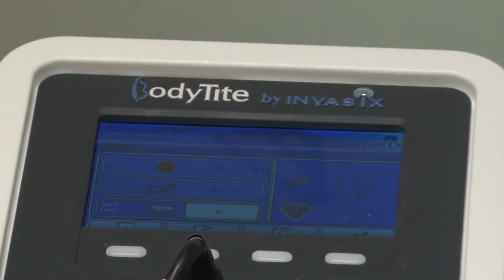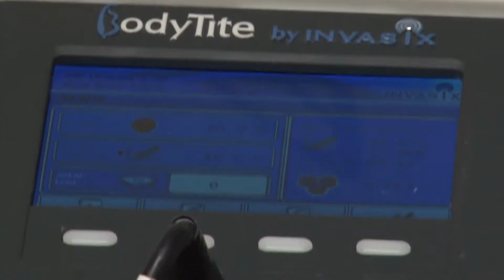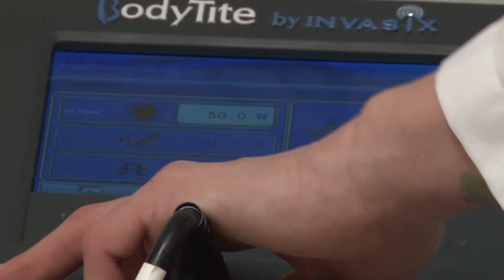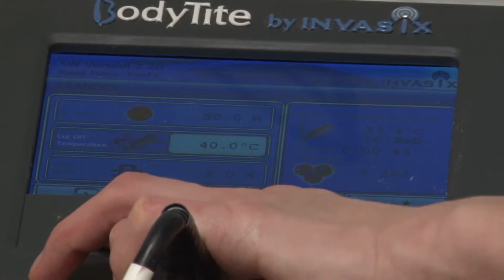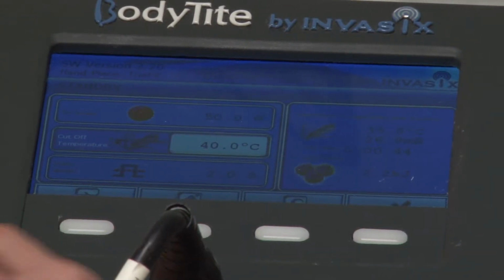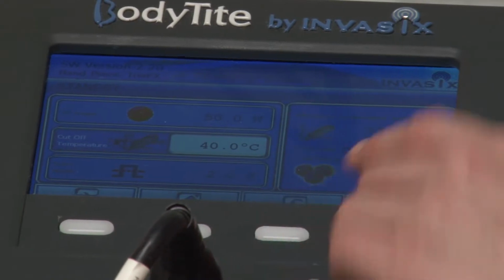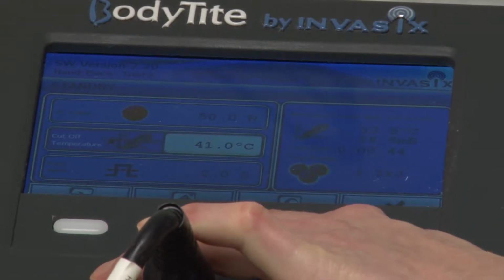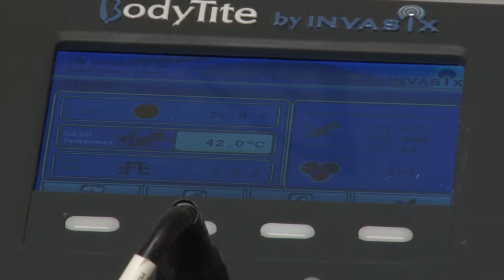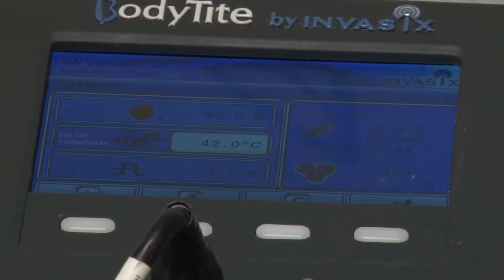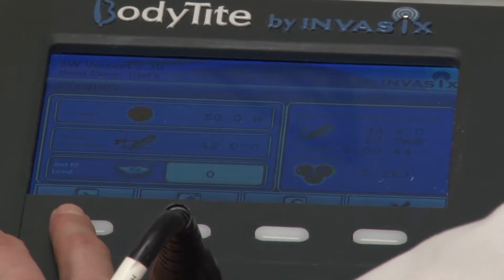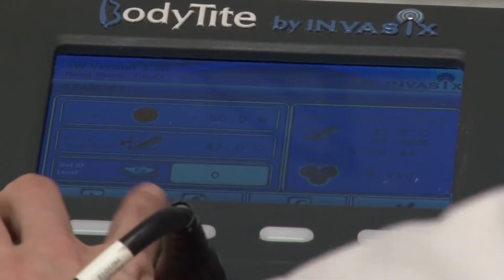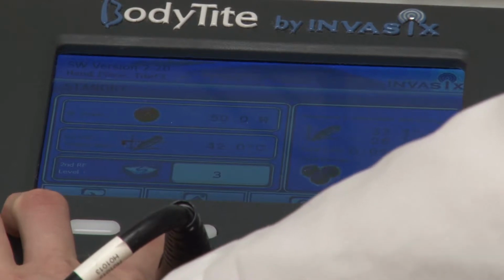Wait, let's go back, show the machine now. Zoom in on the console and tilt down a bit. Excellent. Now slowly move in and go to the temperature setting. So use the menu button. Tilt your hand down because we can't see. Come around the applicator. There you go. Now come under the applicator. That's it. And now we're at temperature. Now go over to the up button. You raise the temperature up to 42 degrees. And let's give her some basic second RF. Go to the menu button under the cords. Beautiful. And now go up to 5. Go slowly up to 5. There's 1, 2, 3, 4, 5.